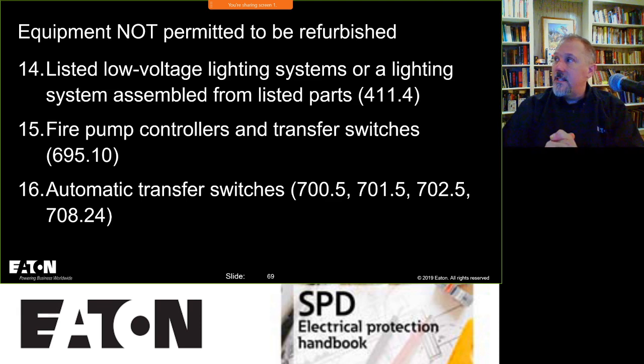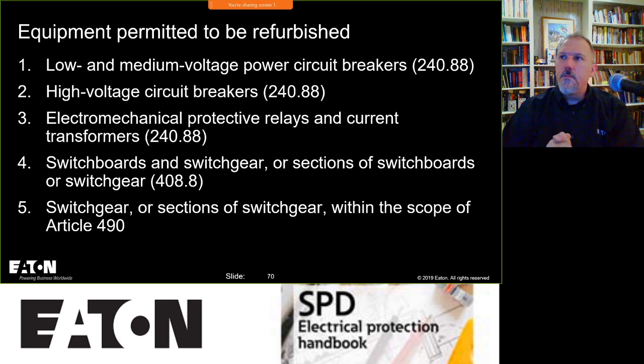Equipment not permitted to be refurbished: listed low voltage lighting systems, or a lighting system assembled from listed parts, fire pump controllers for obvious reasons, and any of the transfer switches in 700, 701, 702, 708. I've seen people make their own transfer switches. Not good. We're not going to let that happen, and we're not going to let you take an automatic transfer switch, especially a life safety system, or fire pump controllers and fire pump transfer switches, take them apart, fix them, and say, yep, I'm good to go. That's just ungood. Gotta see if ungood's a word too.